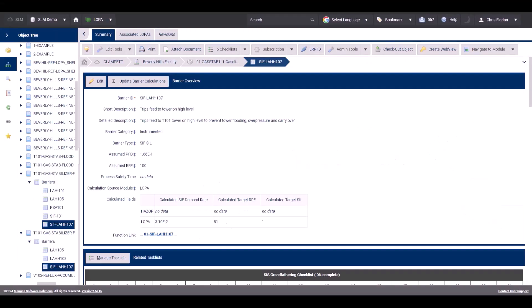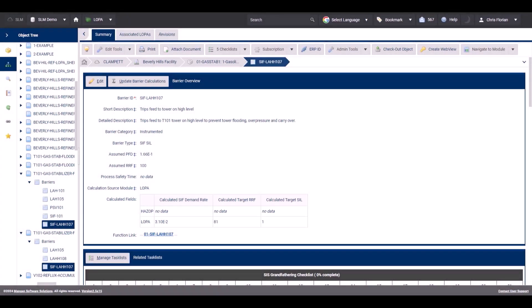The first of the three groups of data is the target risk reduction factor, target probability of failure on demand, and target safety integrity level. In the LOPA module, navigate to the IPL object. The calculated fields table displays the calculated target risk reduction factor and calculated target safety integrity level values. The target RRF and PFD for a SIF is calculated in the LOPA module based on the scenarios it's applied to and the remaining gap for each of these scenarios. For more information on this calculation, see the video on LOPA calculations.